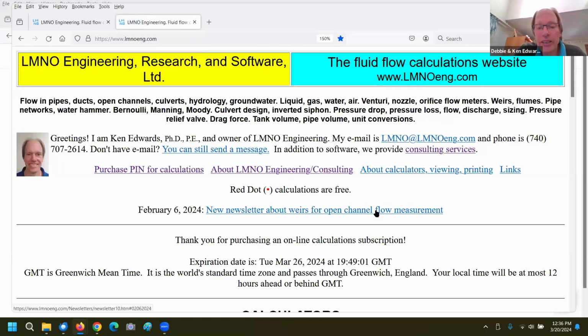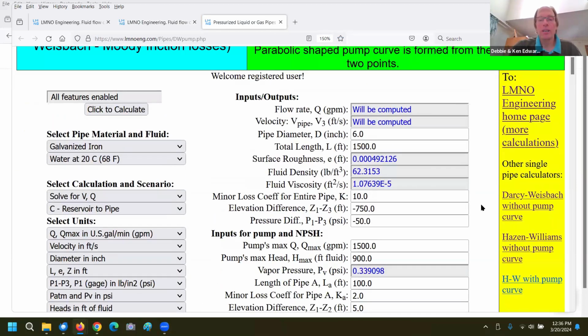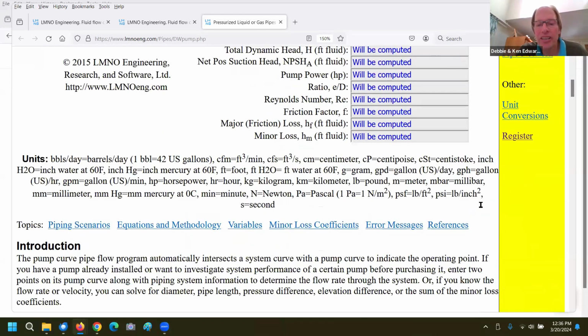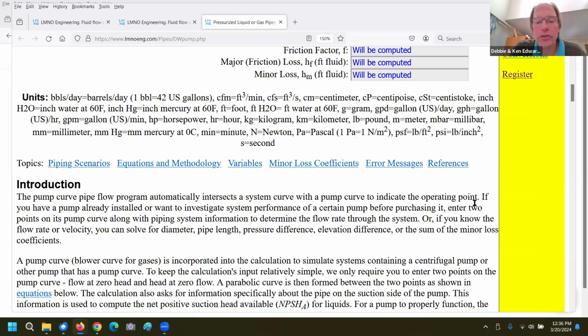So just kind of moving along here, I'm going to click back on the home page. This is kind of a fun one, if you want to include a pump curve. A lot of folks, I'll be told by a client, we need so many gallons per minute, and I'm talking in gallons per minute because that's English units, and that's what I'm familiar with as far as the bigness of them. I apologize if you're in the international community where you're not just doing English units, obviously. Somebody will tell me the gallons per minute of their system and say, here's the system, what size pump do I need? Well, this program is an intersection of the system curve, which is what you get by using the previous program, and actually using a pump curve.